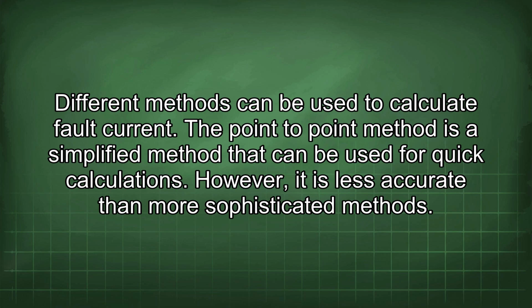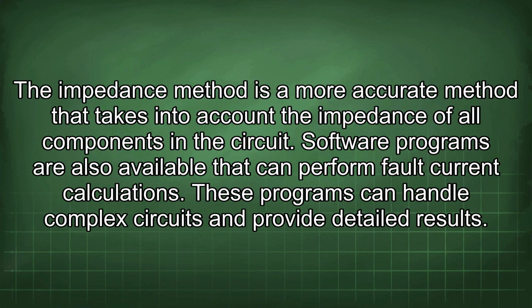Different methods can be used to calculate fault current. The point-to-point method is a simplified method that can be used for quick calculations. However, it is less accurate than more sophisticated methods. The impedance method is a more accurate method that takes into account the impedance of all components in the circuit. Software programs are also available that can perform fault current calculations. These programs can handle complex circuits and provide detailed results.